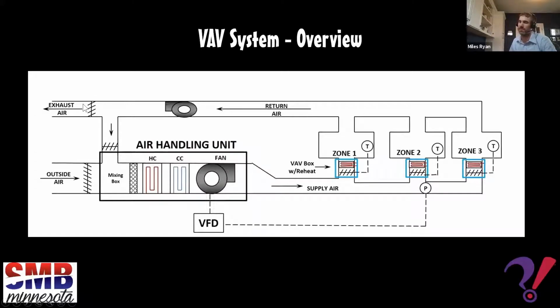And then you have an exhaust or a relief air damper that can modulate to dictate how much air is being relieved from the system. Okay, so the recirculated air and the outdoor air go through a mixing box. They go over a filter to clean up that air. And then we have heating and cooling coils within that air handling unit that are going to be used to essentially get the discharge air or the supply air coming out of the air handling unit to some temperature.